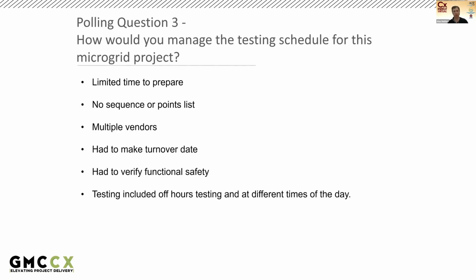So, final polling question. Take a moment and think: how would you test this microgrid? How would you manage the testing schedule for this microgrid project? If you were in our shoes, you had limited time to prepare, drawings are incomplete, there are multiple vendors and parties, and the owner had a strict turnover date with liquidated damages. So no matter what, there's a drop dead date of when the system had to be ready, had to be safe, had to be efficient. Most, if not all, testing had to be live with significant PPE required, and lockout/tagout strictly enforced.